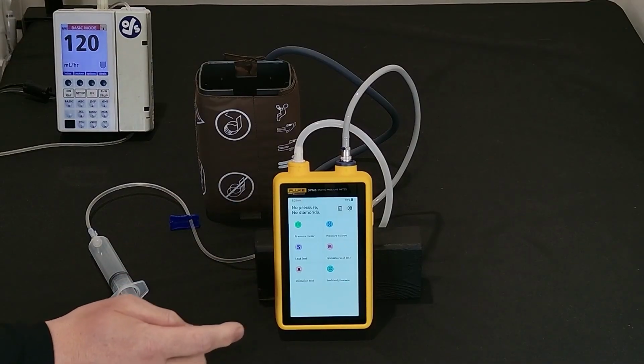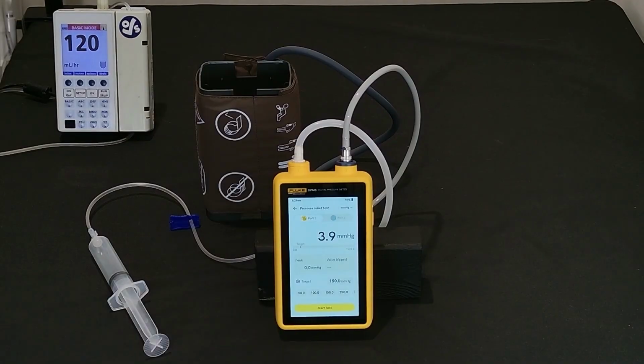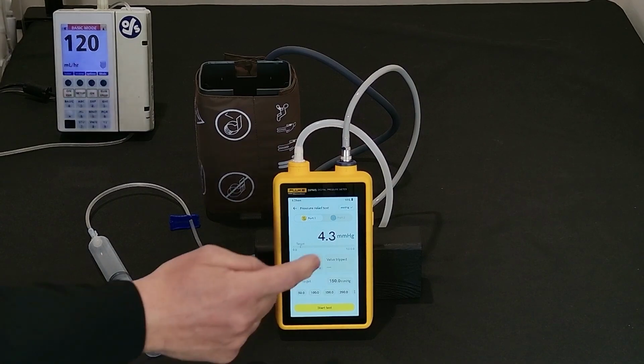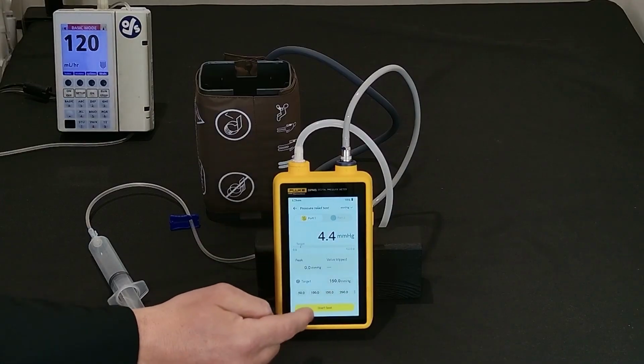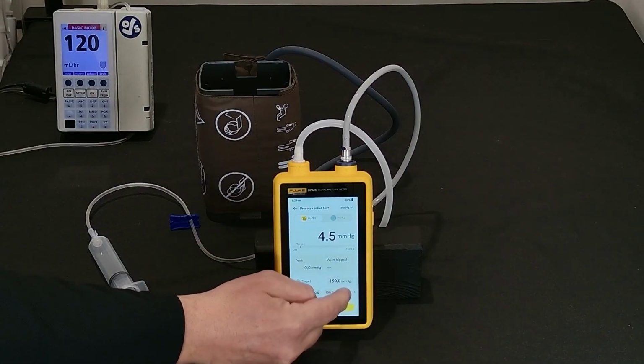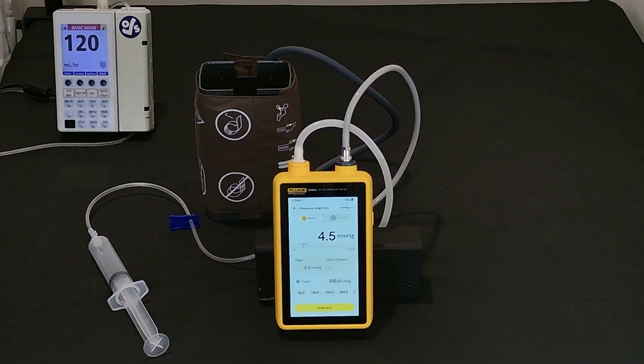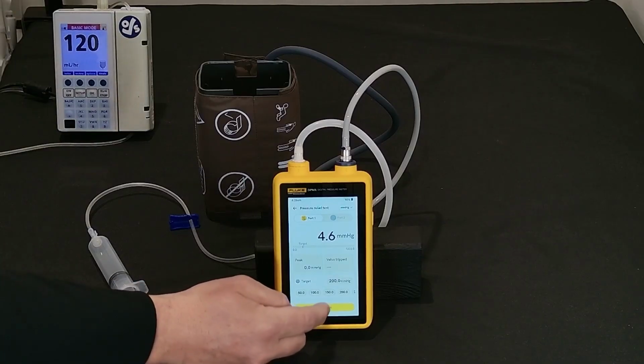Now let's look at the pressure relief test. So here we have a pressure relief test. If you're doing some tests on a piece of equipment that has a relief valve and you're wanting to test it, again, you can select your units of measurement. Here we'll use millimeters of mercury. And then you can select a desired pressure that the relief valve is going to release at. Here we have it set for 200, and we'll start our pump.